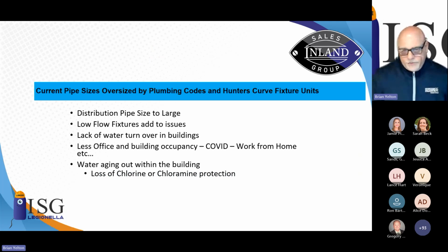We have distribution pipe sizes that are way too big. In the state of Illinois, our piping was designed back in the 70s and early 80s. Well, guess what? What did we flush toilets with back then? 3.5 or 5 gallons per flush. What were our faucets? Way over 2.5 gallons per minute.